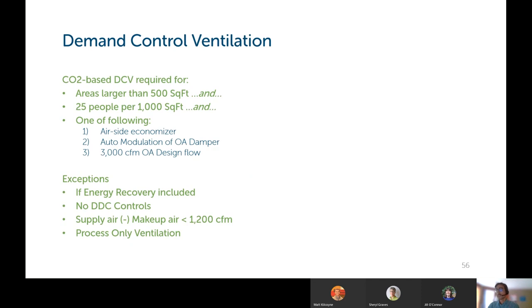Demand control ventilation. This is similar to what was required in the 2015 energy code. You need to have CO2-based demand control ventilation in areas that are larger than 500 square feet and that have an occupant load of 25 people per 1,000 square feet, and that have one of the following systems: either an airside economizer, auto modulation of the outdoor air damper, or these spaces that have 3,000 CFM of outdoor air design flow.